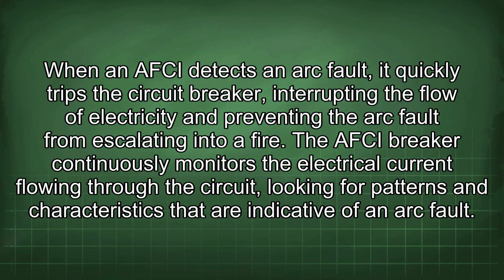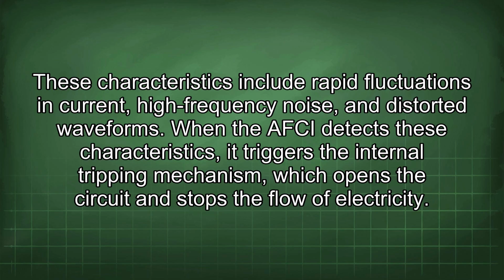When an AFCI detects an arc fault, it quickly trips the circuit breaker, interrupting the flow of electricity and preventing the arc fault from escalating into a fire. The AFCI breaker continuously monitors the electrical current flowing through the circuit, looking for patterns and characteristics that are indicative of an arc fault. These characteristics include rapid fluctuations in current, high-frequency noise, and distorted waveforms. When the AFCI detects these characteristics, it triggers the internal tripping mechanism, which opens the circuit and stops the flow of electricity.